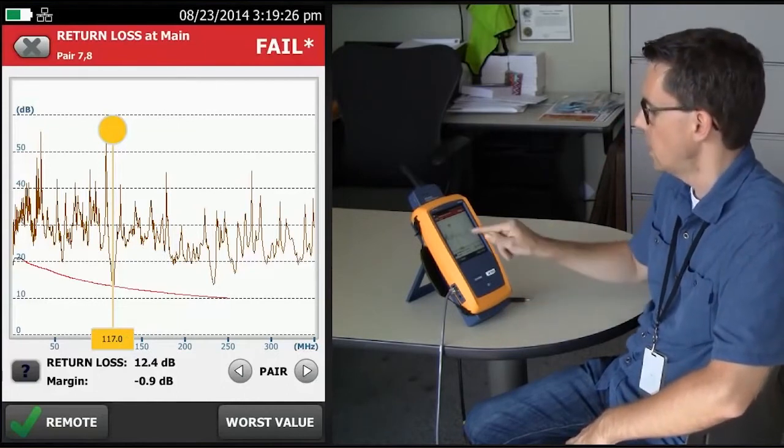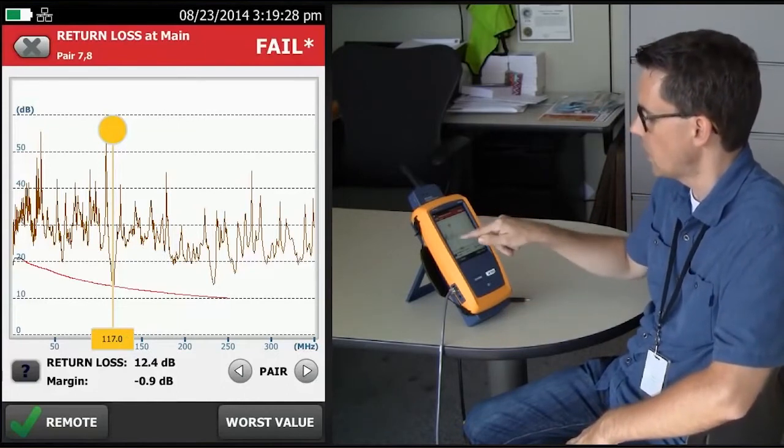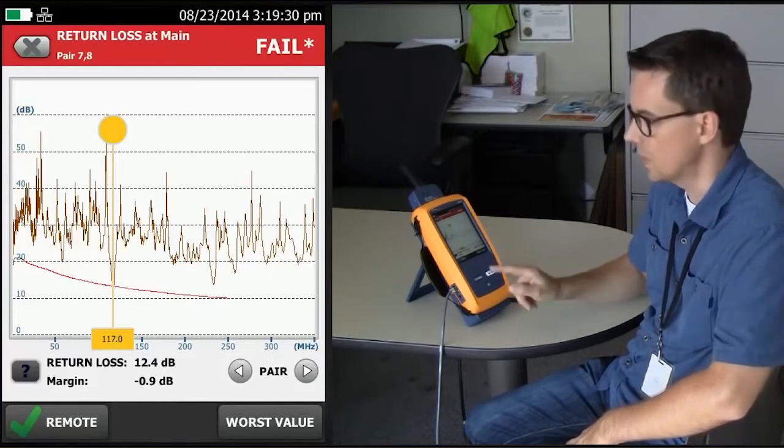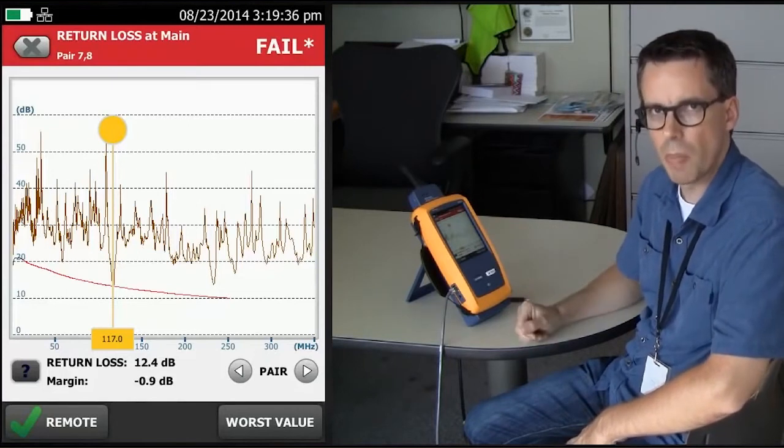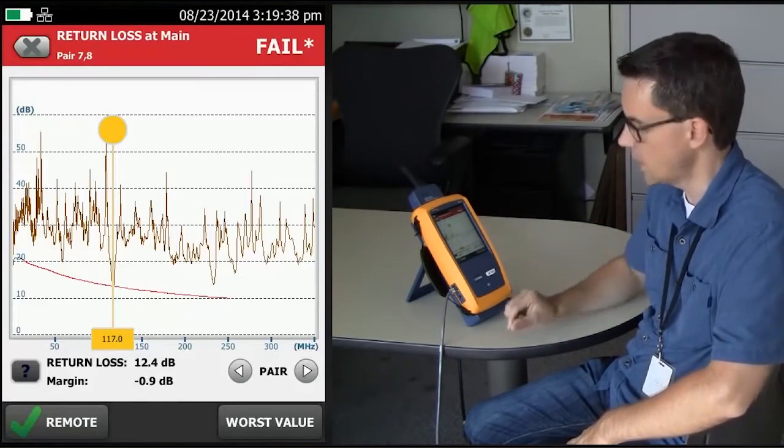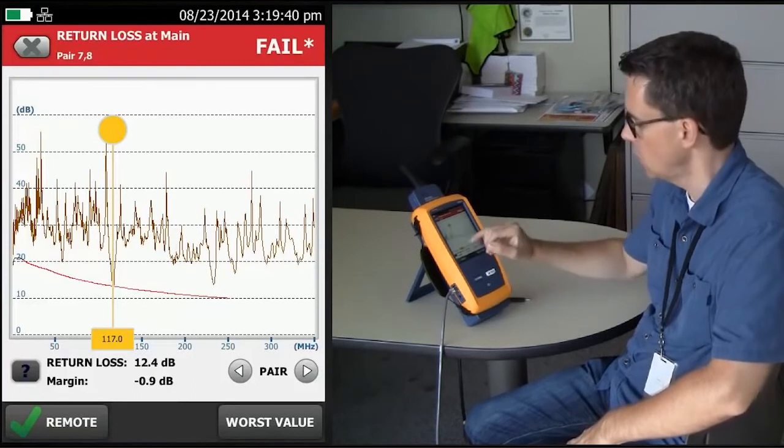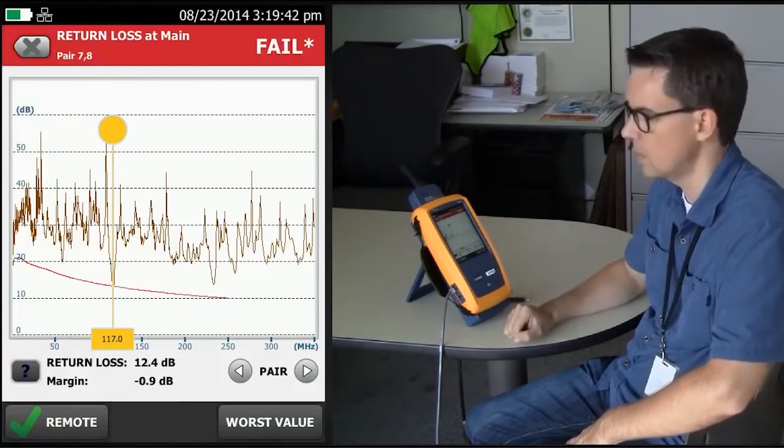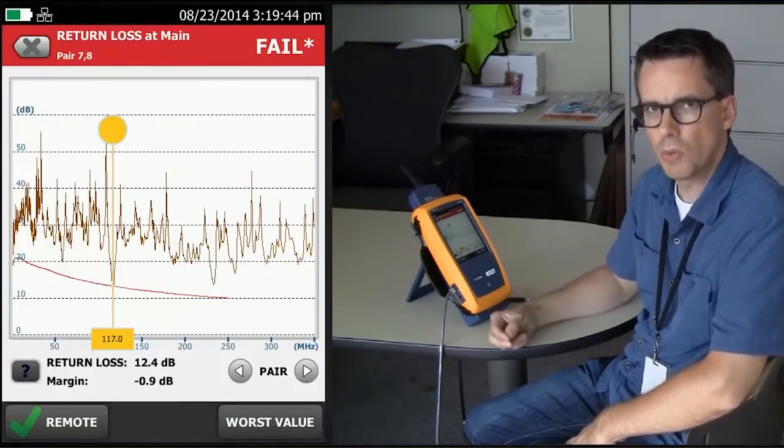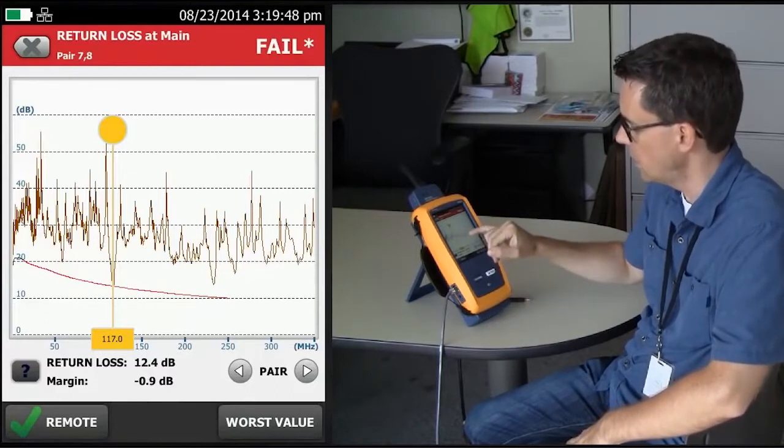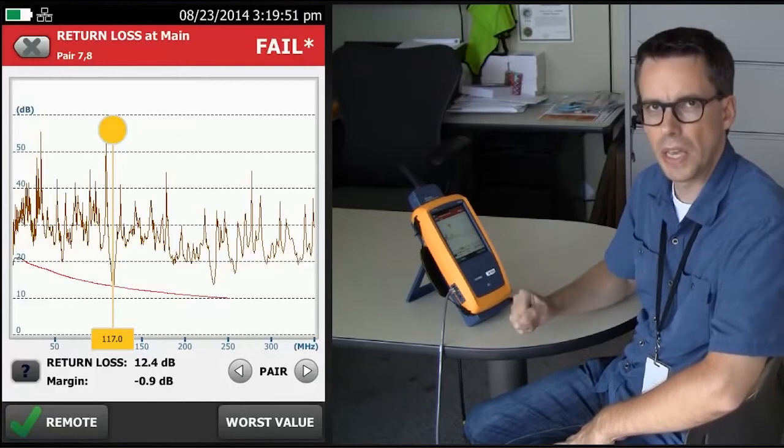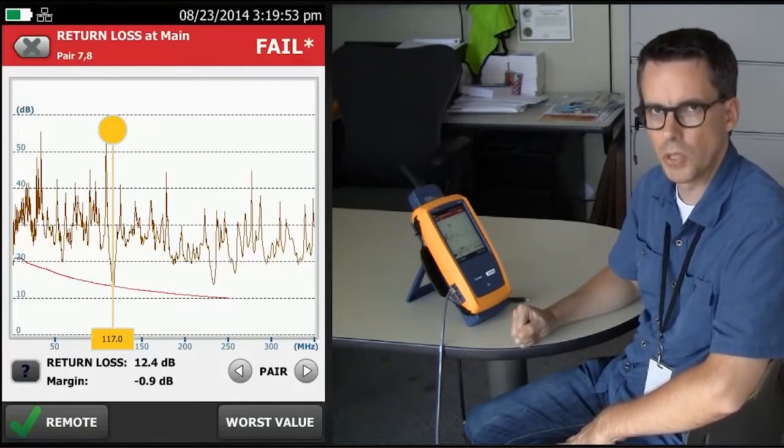However, there is something to be told about this screen here, because when you look at each side of the cursor, the rest of the frequency response is actually passing. It's above the test limit with good margin. It's just happening at this one frequency point. When you see a return loss fail at a single point frequency like this, and everything else is passing with good margin, that's an indication of a cable issue.